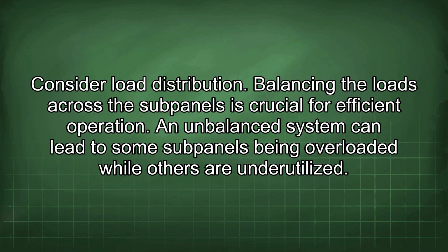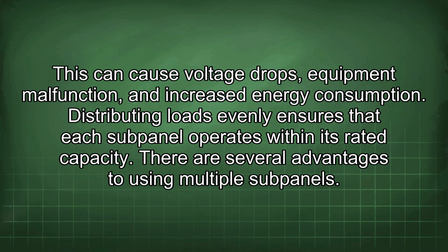Consider load distribution. Balancing the loads across the subpanels is crucial for efficient operation. An unbalanced system can lead to some subpanels being overloaded while others are underutilized. This can cause voltage drops, equipment malfunction, and increased energy consumption. Distributing loads evenly ensures that each subpanel operates within its rated capacity.